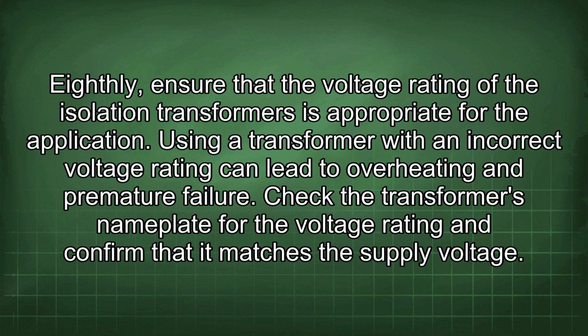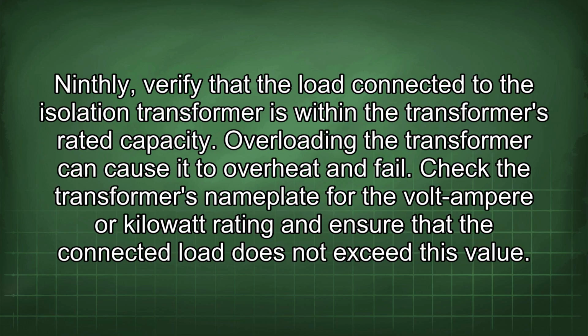Eighthly, ensure that the voltage rating of the isolation transformers is appropriate for the application. Using a transformer with an incorrect voltage rating can lead to overheating and premature failure. Check the transformer's nameplate for the voltage rating and confirm that it matches the supply voltage. Ninthly, verify that the load connected to the isolation transformer is within the transformer's rated capacity. Overloading the transformer can cause it to overheat and fail.